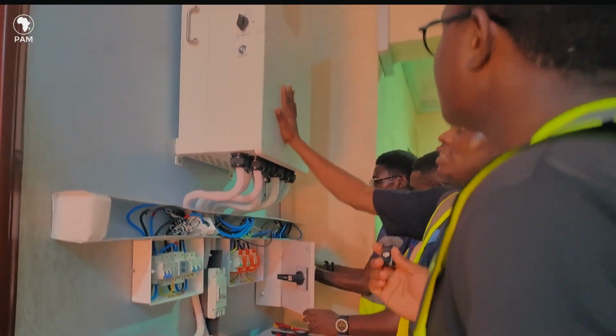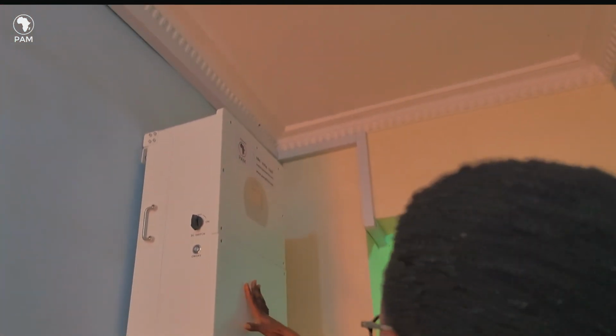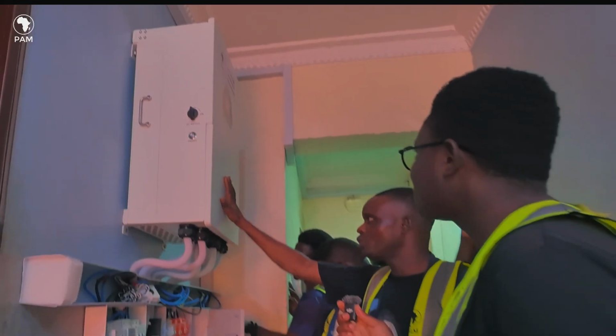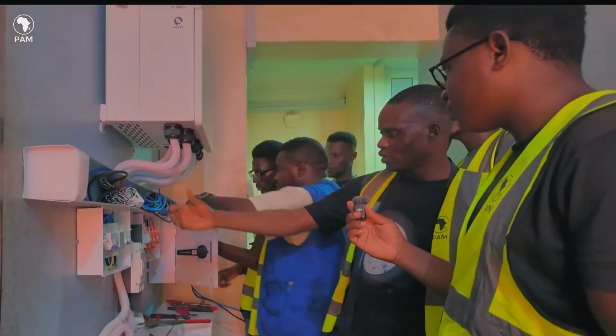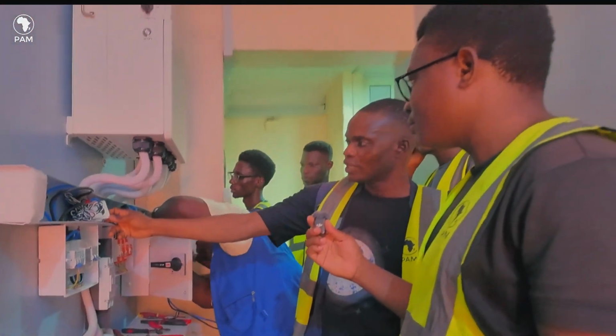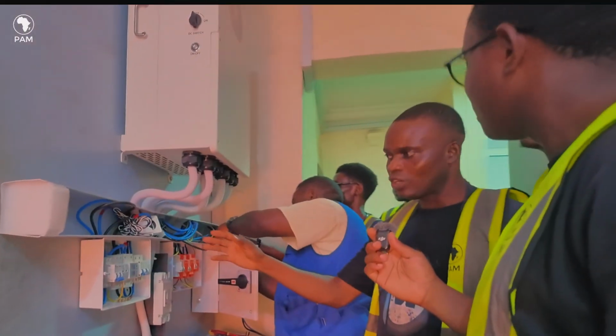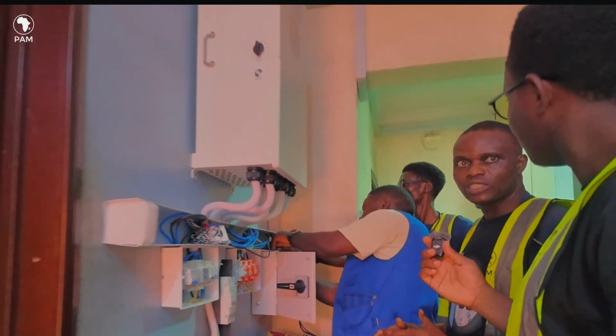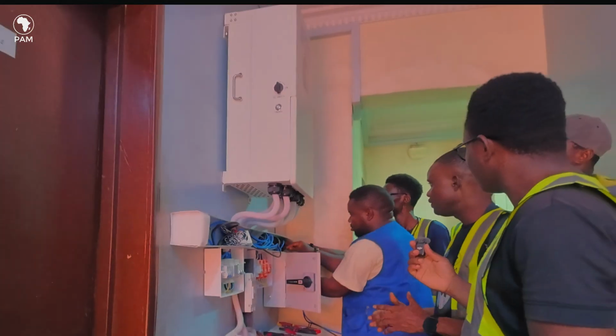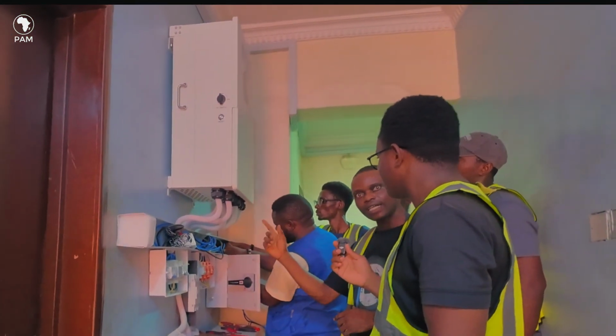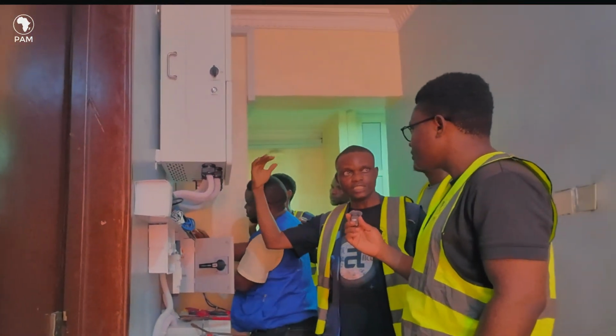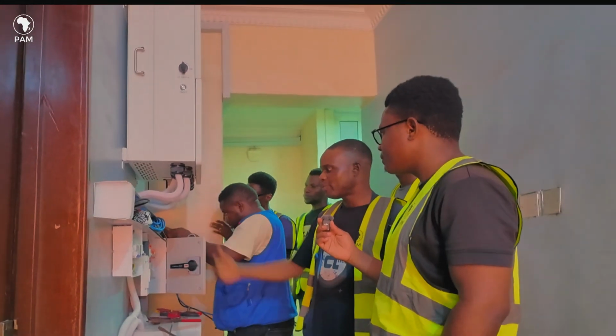And here we have the machine itself, a smart hybrid inverter rated 16 kilowatts by 48 volts. We've applied the CT current transformer to ensure it doesn't feed into the grid, and also to optimize performance so the solar is prioritized. It doesn't pull from the grid; rather it prefers using solar power as first priority.